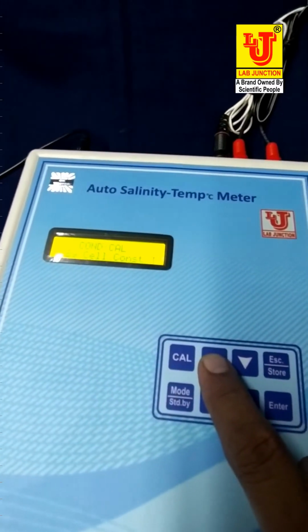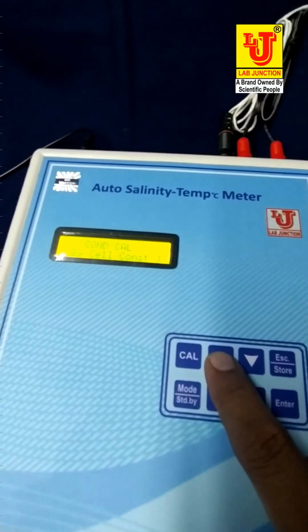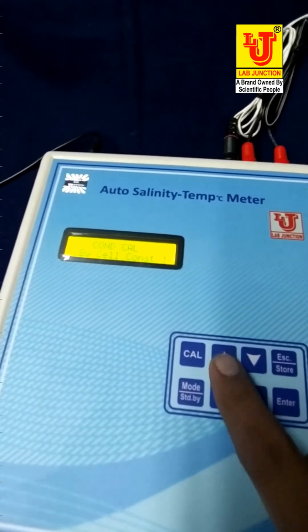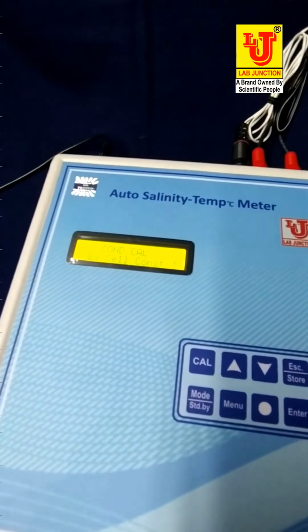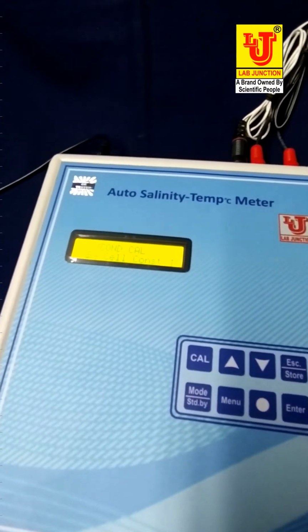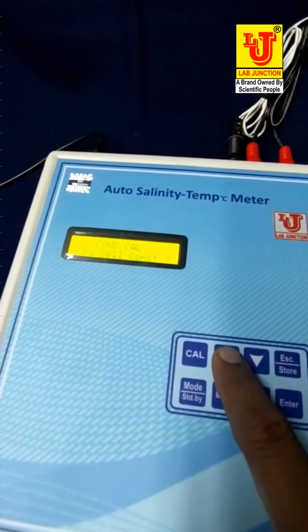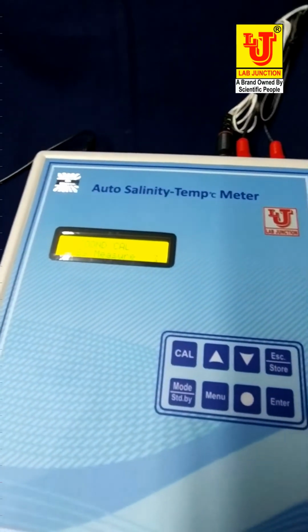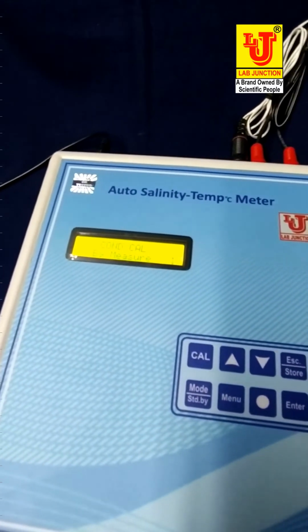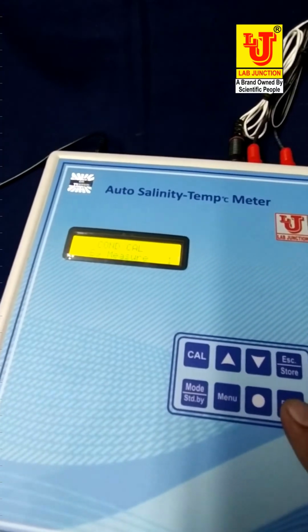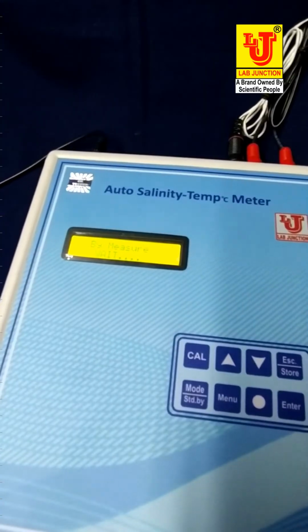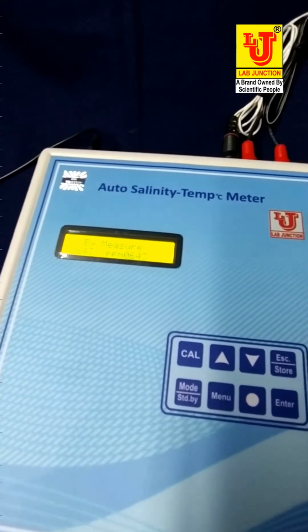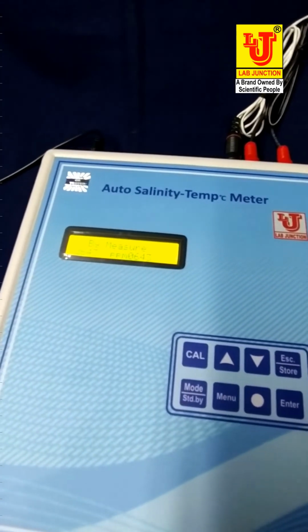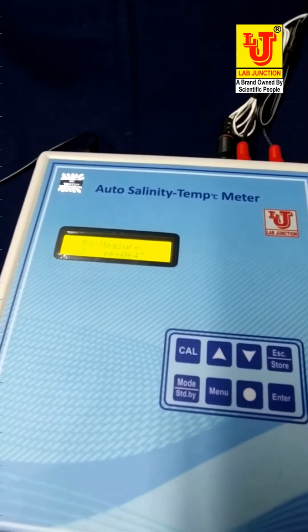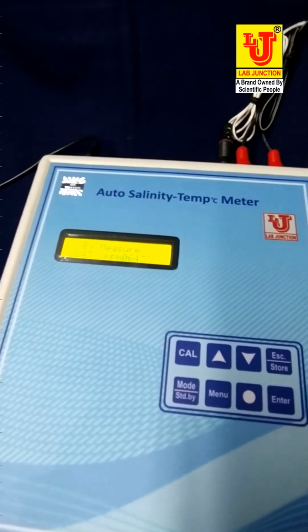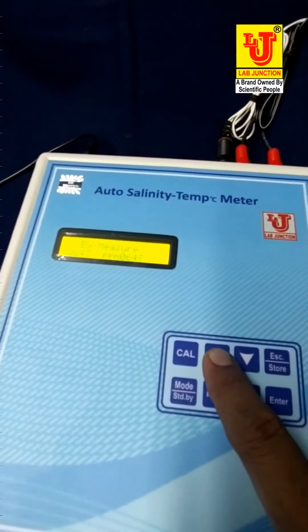If you want to do by cell constant, then you have to feed the value of your salinity cell constant value. Suppose it is 1.000. Now I am pressing up key. I am calibrating this by measure method. Now you have to press enter. Now value is 643 ppm and my known salinity standard solution value is 750 ppm. Then you have to feed your known salinity value like this.